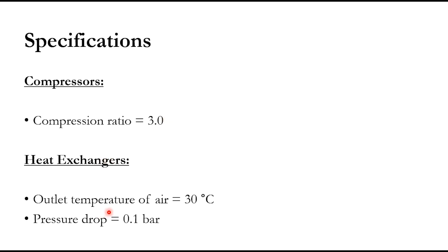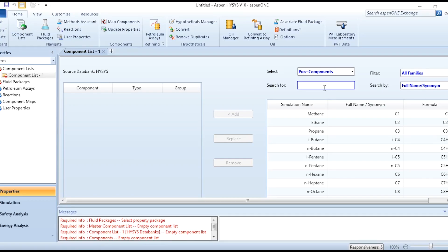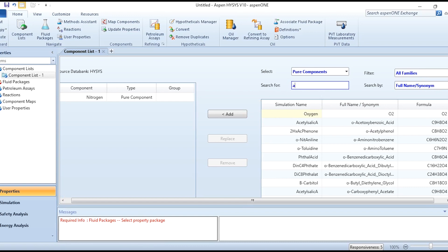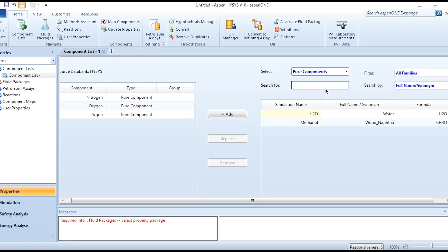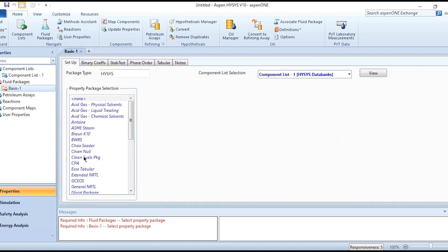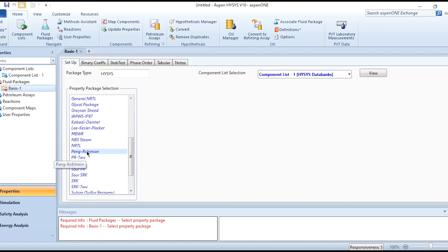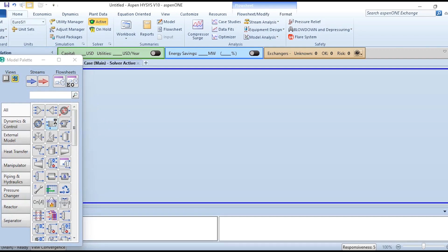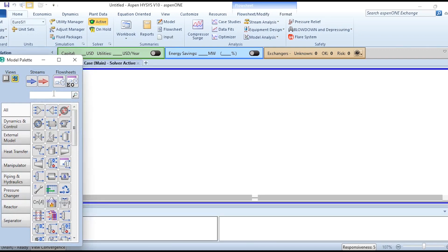For the heat exchangers, the outlet temperature of air in both the intercooler and after-cooler is 30°C, with a pressure drop of 0.1 bar on both shell side and tube side. Now going to Aspen HYSYS to simulate the process — we will add components nitrogen, oxygen, argon, and water, and select Peng-Robinson as the fluid package for the air system.